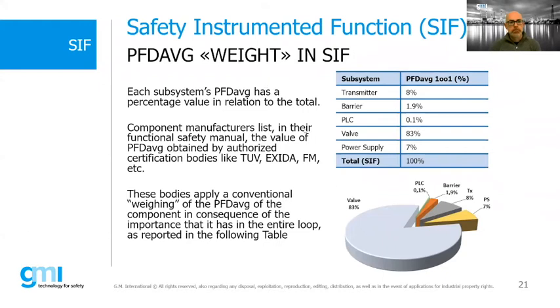In the following slide, we see what weight the individual subsystems have within a SIF. It's important that every single component of a SIF, including the power supply system, is included in the PFD average calculation to achieve the required safety level. Every single element has its own percentage weight, which must be considered.